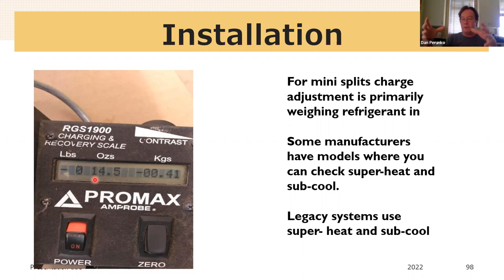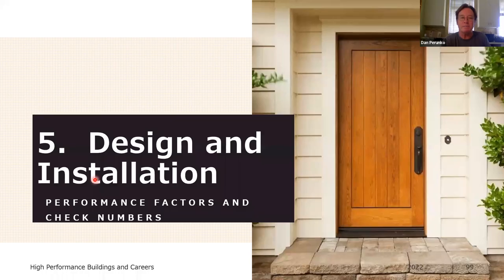And what you're doing is you're letting refrigerant out of the bottle on the scale into the mini split while it's still under vacuum, right? So the refrigerant wants to get sucked into the system. And there's a calculation provided by the manufacturer based on the length of the line set that tells you how much refrigerant you need to add.